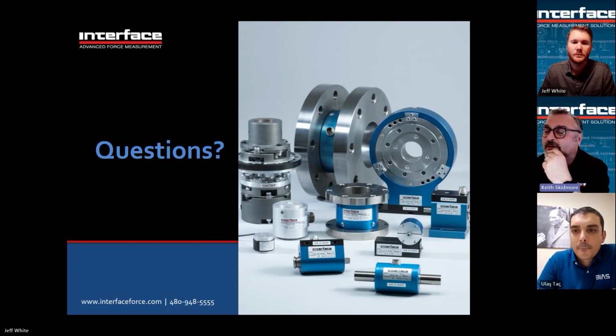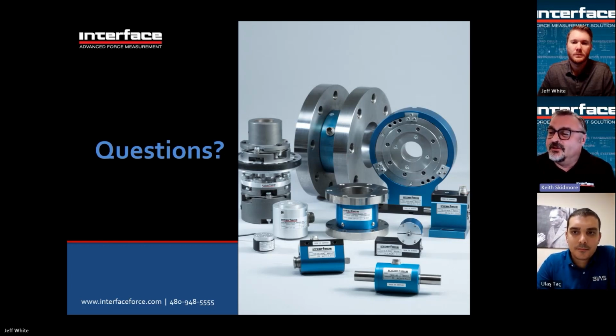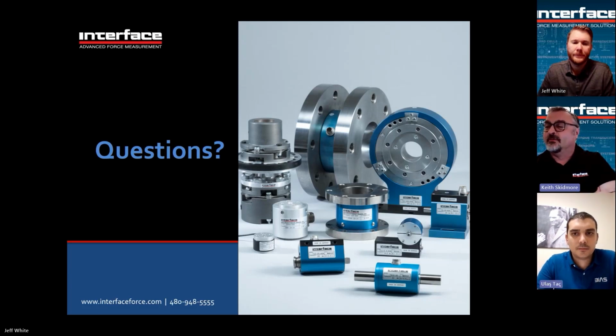That's a very good question. Three-phase motor, better than a one-phase motor. If the nominal torque is 300 Newton meters, you could easily exceed 500 Newton meters under certain conditions, say startup or stop if there's a lot of inertia, depending on what's being driven. You have a motor, but what is being used as the load? So I would say you certainly wouldn't want to use a 300 Newton meter sensor. 500 may be okay. 1,000 Newton meters might make more sense, but you do have to consider not only the motor, but what is being tested. Is it a gearbox? What happens if it fails?